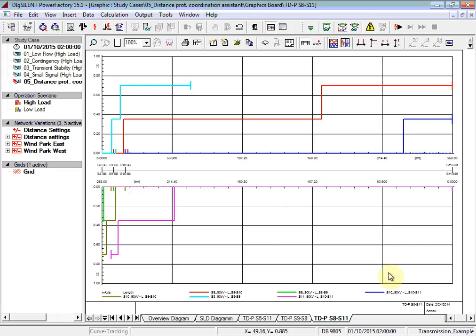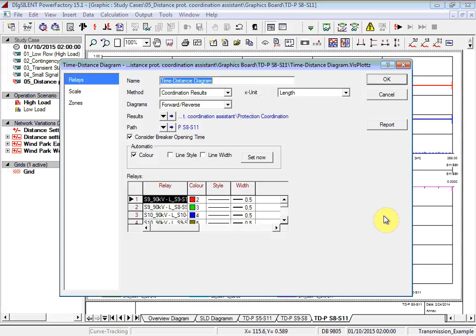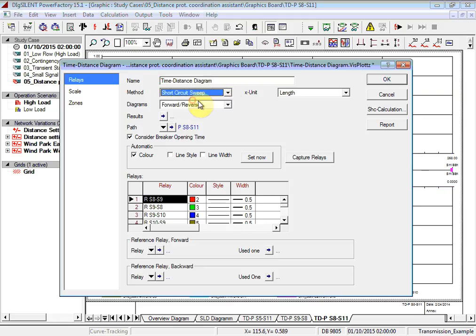The time distance diagrams illustrated are ideal time distance diagrams. They do not take into account the influence of other relay settings and other issues introduced by the network topology. Now that we've written the settings back to the devices, let's see what the real performance of the relays will be under short circuit calculation conditions. Double click on the diagram and change the method from coordination results to short circuit sweep.